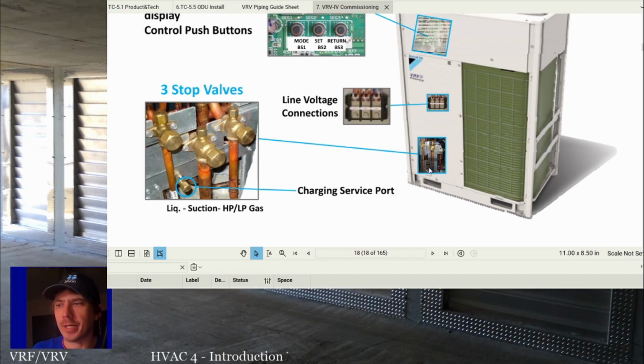Now, another quick digression. Some units, some systems, especially older ones, will have a fourth line coming out of the outdoor unit. That fourth line is an oil equalization line. And that's for if you've got, say, three outdoor units. A lot of these systems, one of the complicated things about VRF, because it's such a big piping system, and one of the complicated things about refrigerant piping in general is returning oil. Okay. The reason you can't run a 2-ton system with an inch and an eighth suction line is because the refrigerant will not be moving back to the outdoor unit fast enough to properly return the oil to the system.